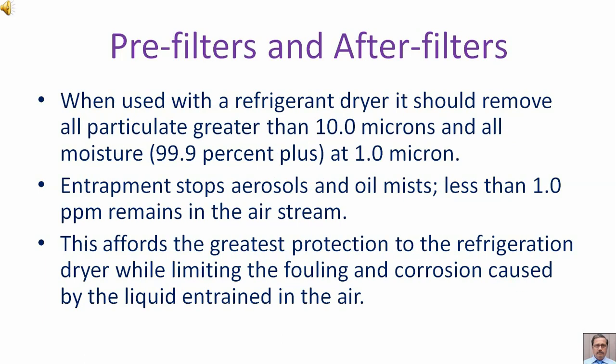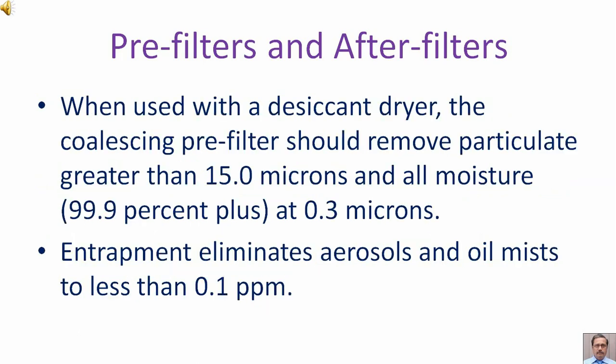When used with a refrigerant dryer, the coalescing pre-filter should remove all particulate greater than 10 microns and all moisture — 99.9%+ at 1 micron entrapment — stopping aerosols and oil mists so less than 1 ppm remains in the air stream. This affords the greatest protection to the refrigeration dryer while limiting fouling and corrosion caused by liquid entrained in the air.